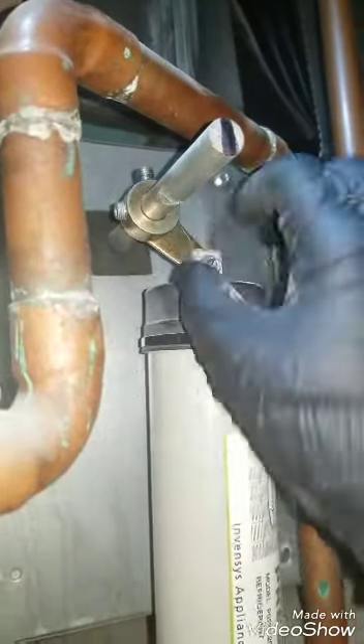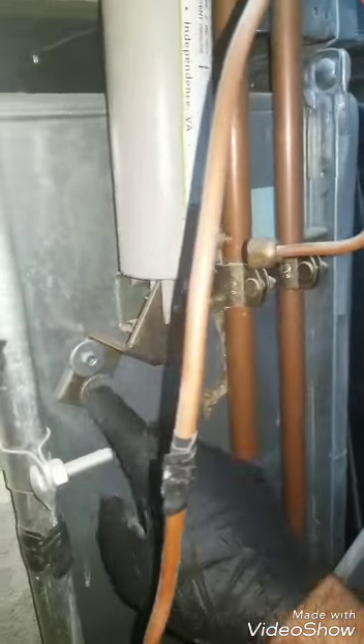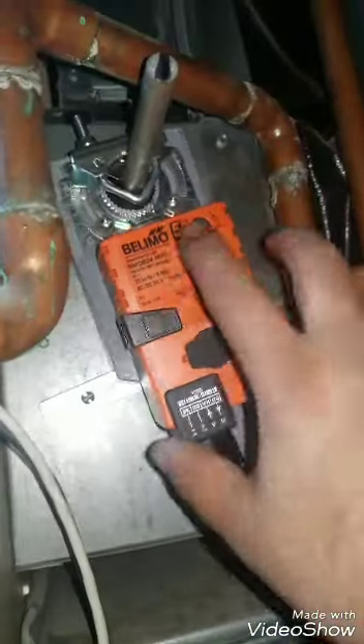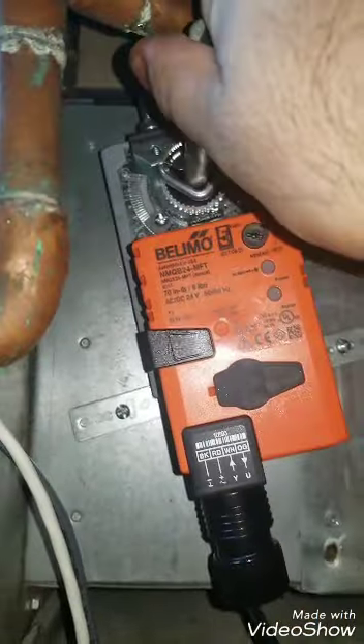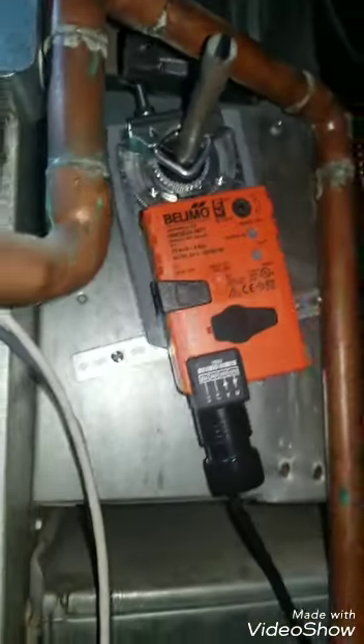Step 3. Once the system's empty, put a T on there. Take off the existing capillary off the Robert Shaw piston. Remove these set screws. Screw right here. Take the whole Robert Shaw piston off. Step 4. Mount your pressure transducer on the T. Step 5. Mount your Belimo actuator where the existing Robert Shaw piston was.